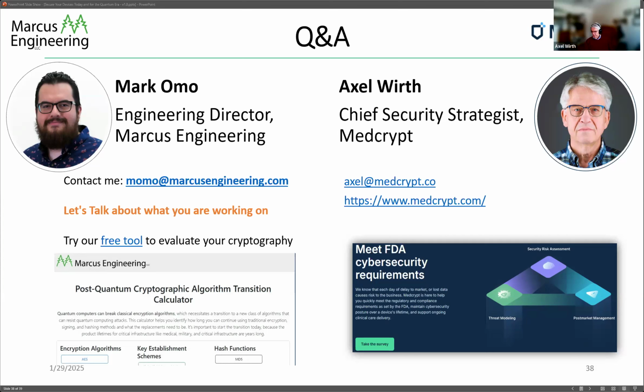And then maybe the last question here, because we come to the end of time, there was one question further up in the chat about de-identified information, where it's a point-to-point connection and there's no patient data in the data stream. Does that still require cryptography? And the answer is it depends. First of all, cryptography is not only used for confidentiality protection, which is what you address through de-identification, but also for integrity protection and authenticity of a data flow. So that is an additional consideration.